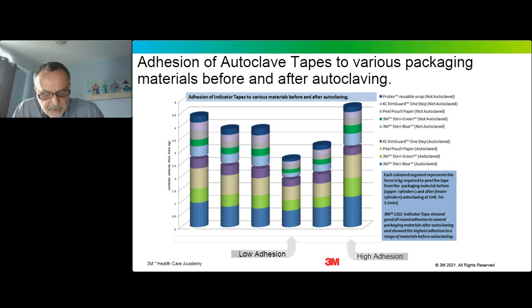In all cases, the peel strength of each tape was lower before than after autoclaving, which is ideally really what we want to observe. We want to know that the tape will cure a little bit after it's been applied, and during the autoclaving process that it will form a good solid seal with the packaging materials for subsequent storage. It is also clear, as shown by the height of each drum, that some tapes have an overall better adhesion to surfaces than others. So if we look at this fourth set of drums from the left-hand side, then you can see the overall adhesion was much lower with that particular product than, for example, the very final drum on the right-hand side, which has very high adhesive properties to all surfaces.